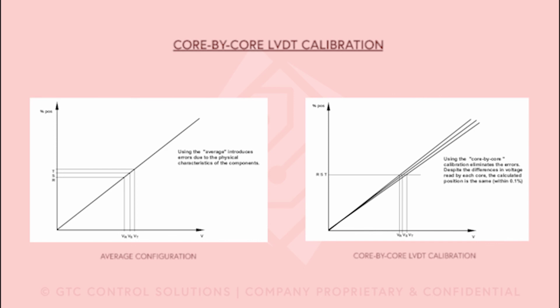This is a problem particular to the Mark V, because Mark IV does core by core calibration automatically, and GE went back to the core by core calibration in the Mark VI and the Mark VI-C, basically using the Mark IV style of calibration of LVDT feedback. We can go into more detail of how to do proper calibrations of all the devices for all the panels, and we have developed very interesting procedures to do this calibration and have very precise results.